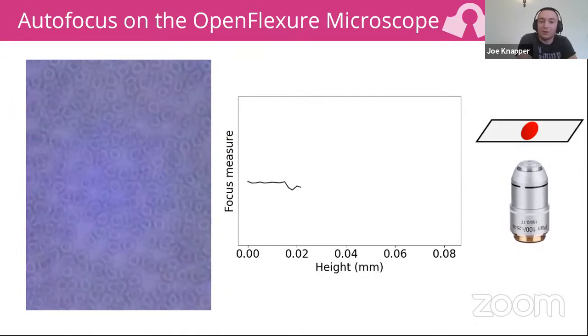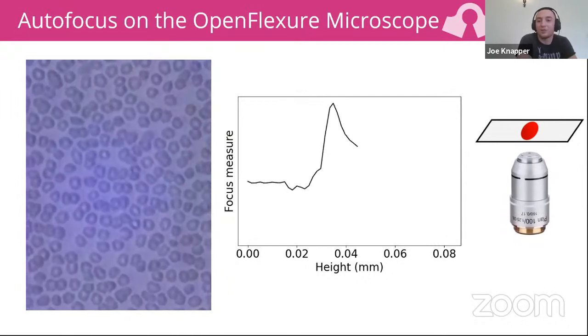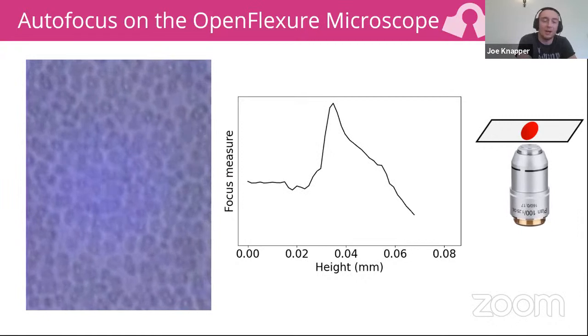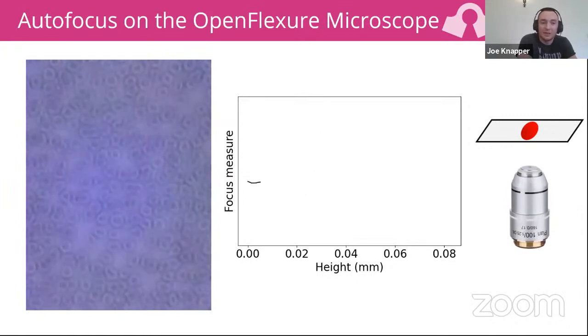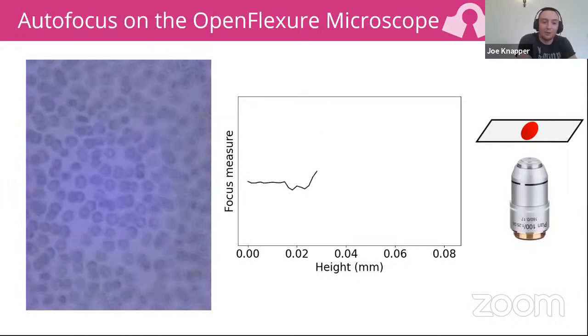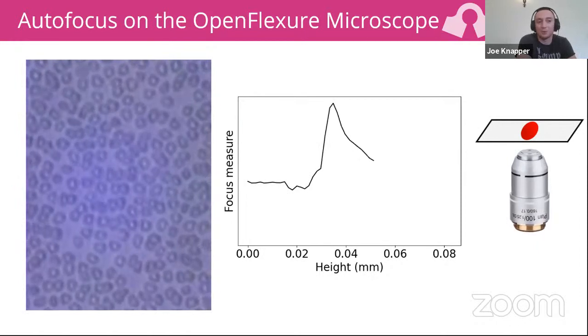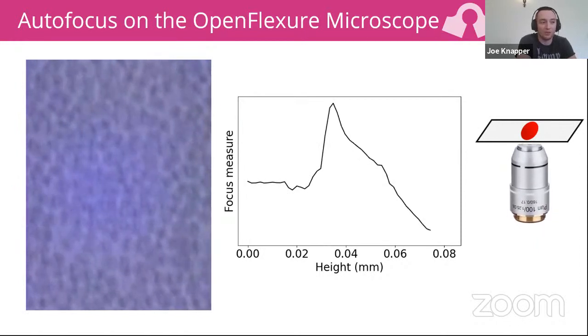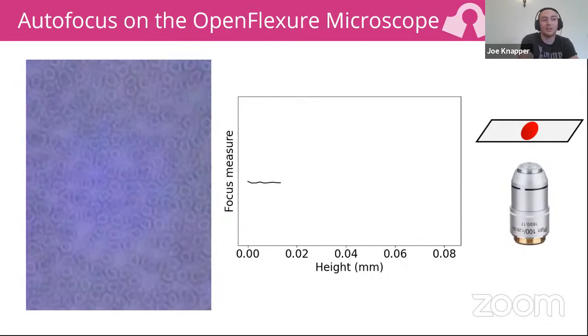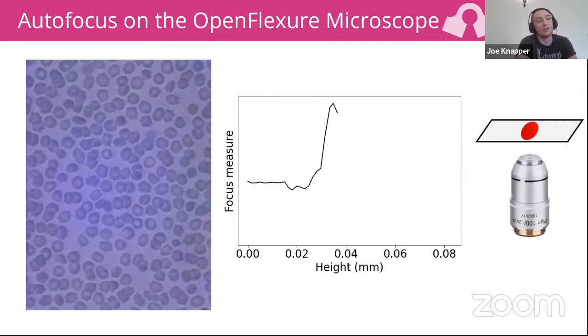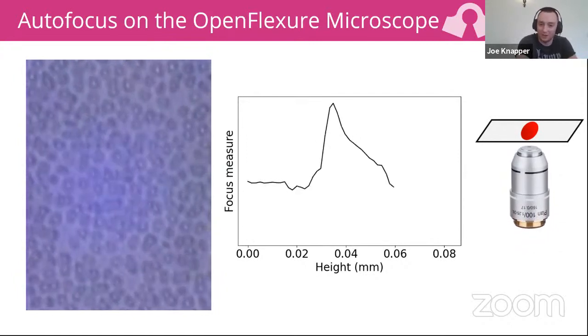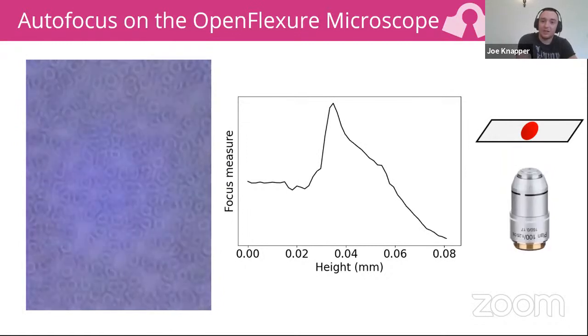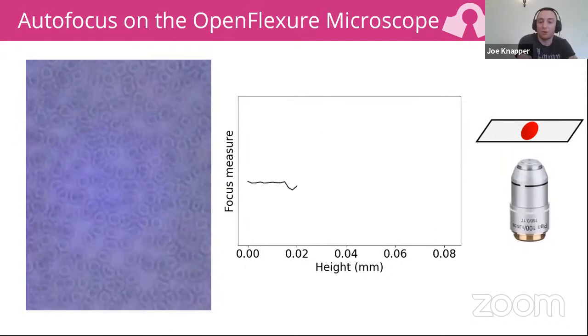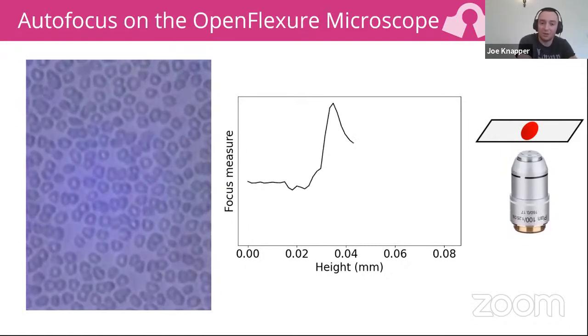As you saw, the standard autofocus takes around 4 seconds and is accurate to within about 3 microns of the focal plane. An autofocus on a digital microscope works by moving the optics closer to the sample, tracking the sharpness, and then returning to the position where the sharpness was highest. These steps are sufficient for pretty much all cases, especially at lower magnification.